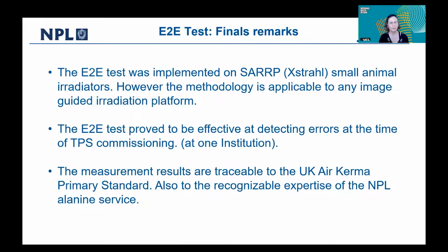So as a summary and final remarks, this end-to-end test was implemented on SARRP small animal irradiators from Xstrahl. However, the methodology is applicable to any image-guided irradiation platform. The end-to-end test proved to be effective at detecting errors at the time of TPS commissioning. At one institution, we managed to spot that. The measurement results are traceable to the air kerma primary standard and also to the recognizable expertise of the NPL alanine service.